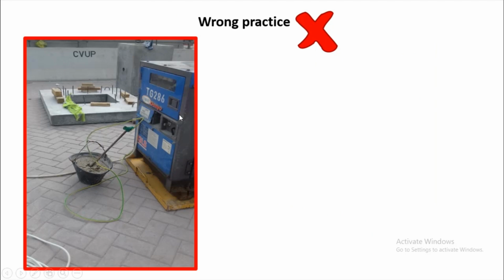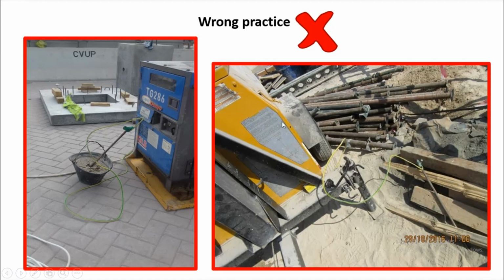So, wrong practice. You have a generator, you provide soil in a bucket, and you insert your earth rod connections into the soil in the bucket. This is not acceptable and is a wrong practice. And you have your generators or tower lights. You have the earthing connection, but your earth rod is not driven into the ground. It is just touching the ground. Okay, this is also an unacceptable practice.